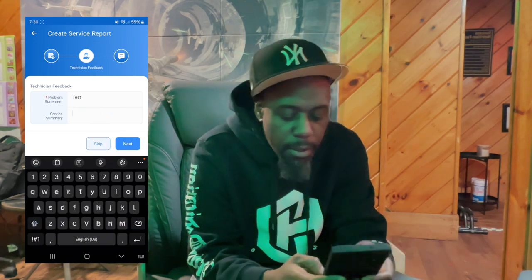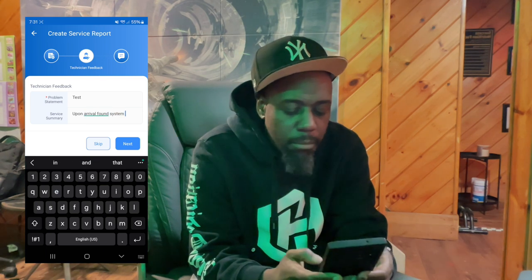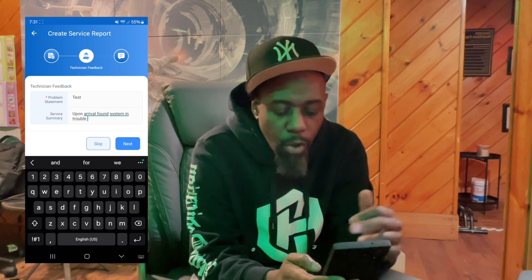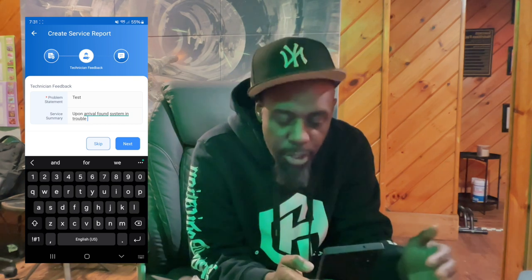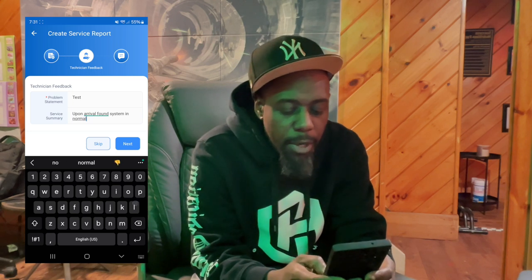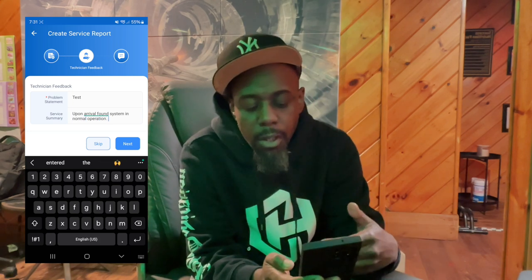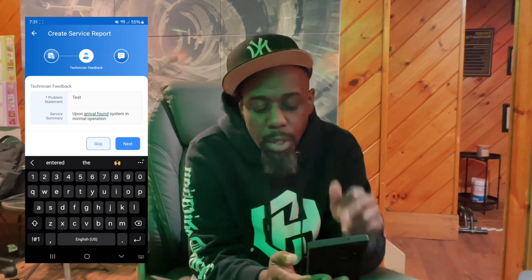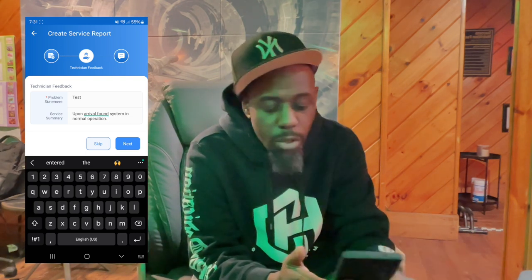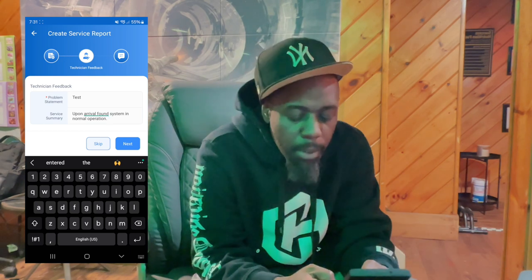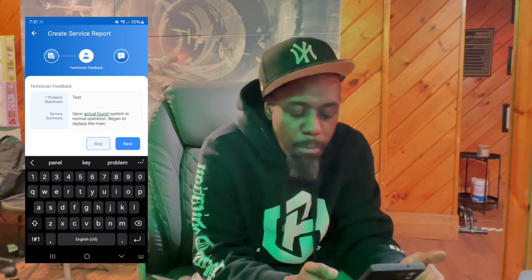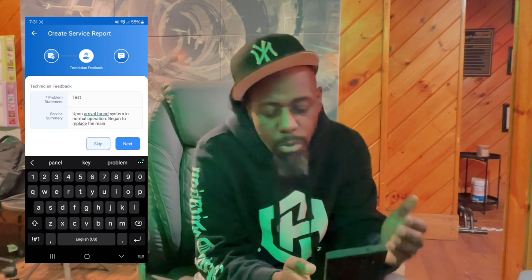Here's the format: you're going to say 'Upon arrival, found system in trouble,' then list the troubles. If you found the system in trouble, record all the troubles listed before you did any work. But if you walked in and found the system in normal operation, that's what you say. For example, if you're going to change batteries and the system was normal, you write: 'Upon arrival, found the system in normal operation.